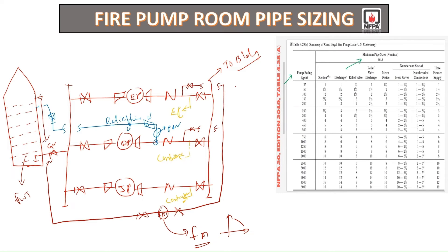Now we will discuss the pipe sizing. For example, if our fire pump capacity is 1500 GPM, when you refer to Table 4.28 you can find that the minimum suction size will be 8 inch. Apart from that, the discharge line will also be 8 inch. These are the minimum sizes that shall be considered.